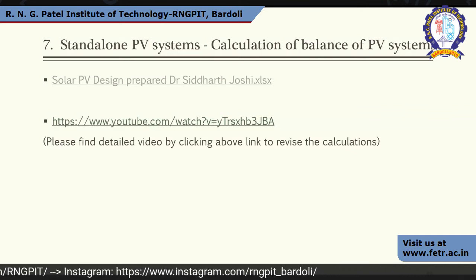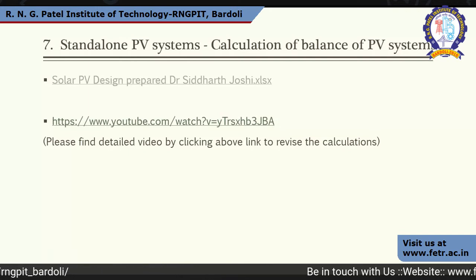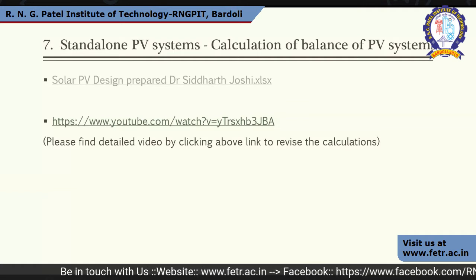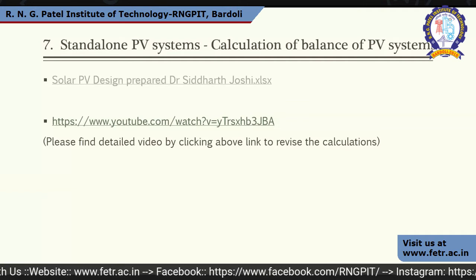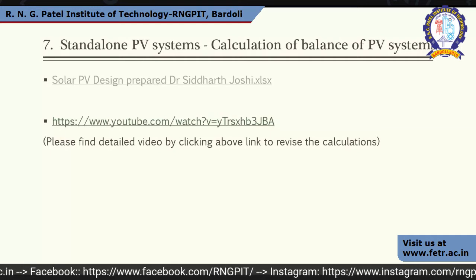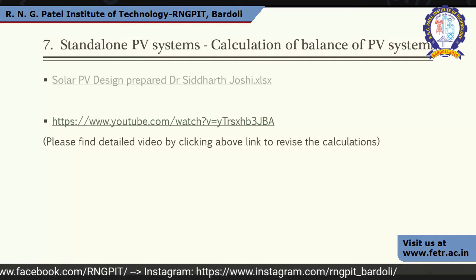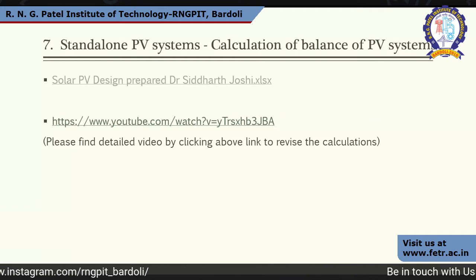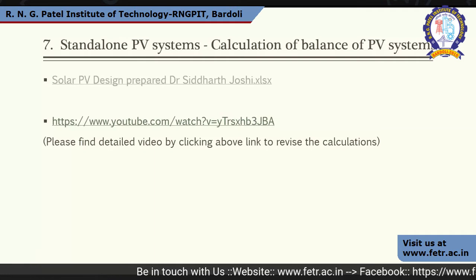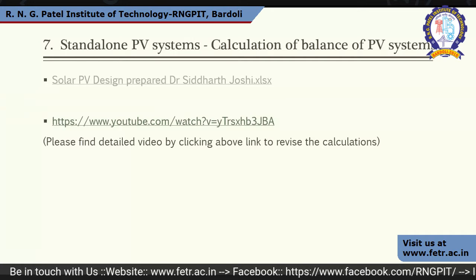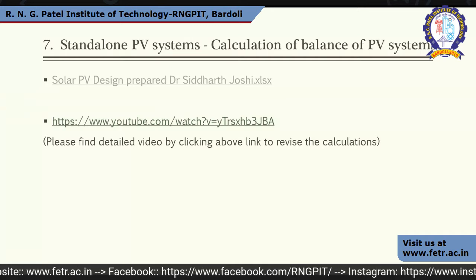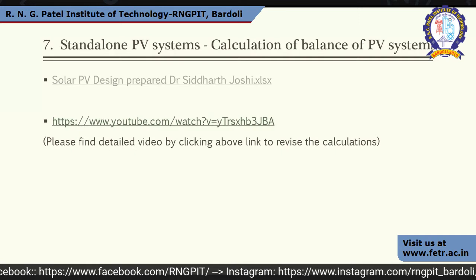Our next component is the charge controller selection and the inverter capacity. As the inverter is a static element, we are assuming the efficiency of the inverter as 96%. In this sheet, the upper and lower caps have also been mentioned based on some field practice experience, though some inverters at constant loading conditions may give above 97%.